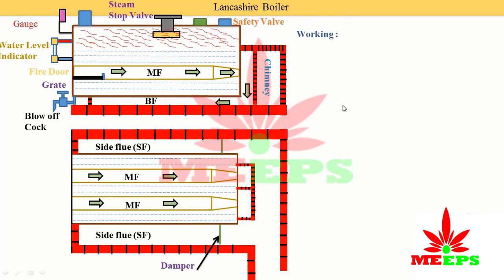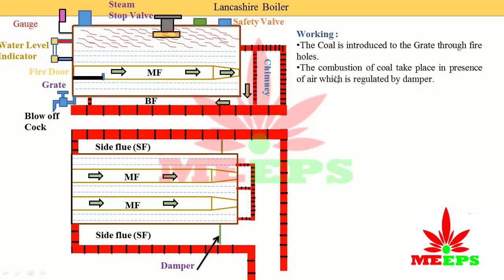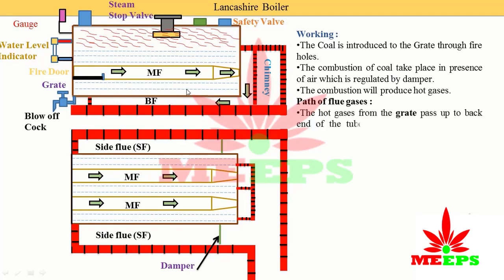Working of the Lancashire boiler: coal is introduced to the grate through the fire door. Combustion of the coal takes place in the presence of air — air supply is regulated by a damper. The combustion produces hot gases, which pass through different components as flue gases. The flue gas first enters the main flue and passes from the grate to the back end of the fire tubes.